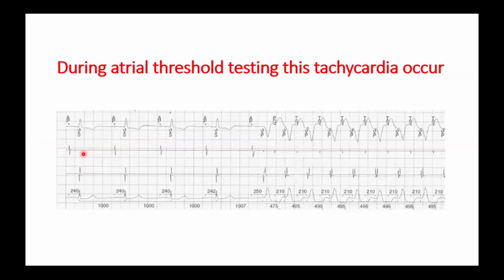As we said before, when there is an intrinsic conduction, we should notice both channels. So there is an atrial pacing followed by ventricular sensing. Notice the ECG here. We are testing in a DDD mode: atrial pacing followed by ventricular sensing. Here, atrial pacing, there is no P wave, so it didn't capture the atrium, followed by ventricular pacing at this long AV interval, and there is a retrograde conduction.